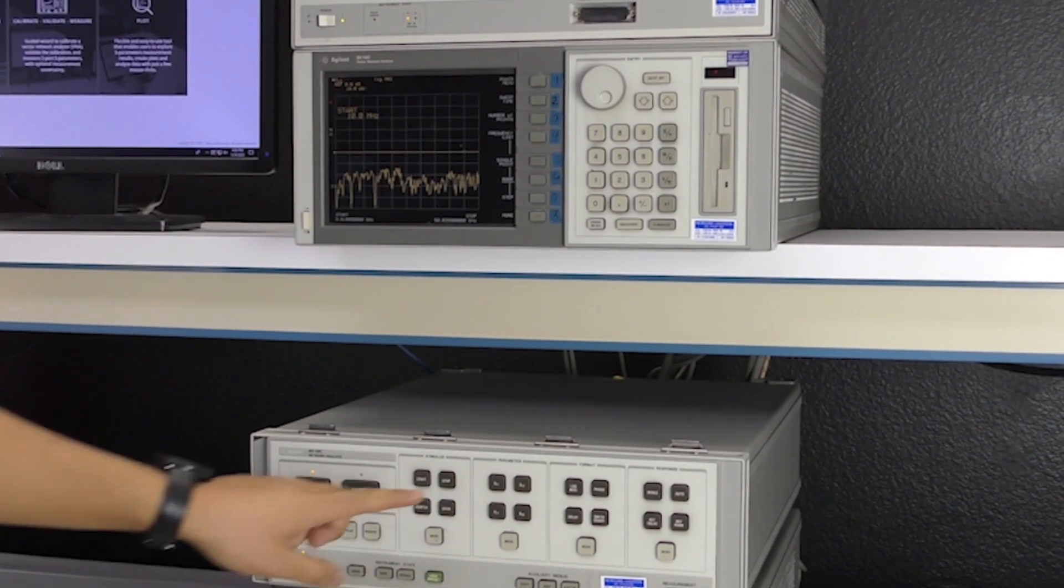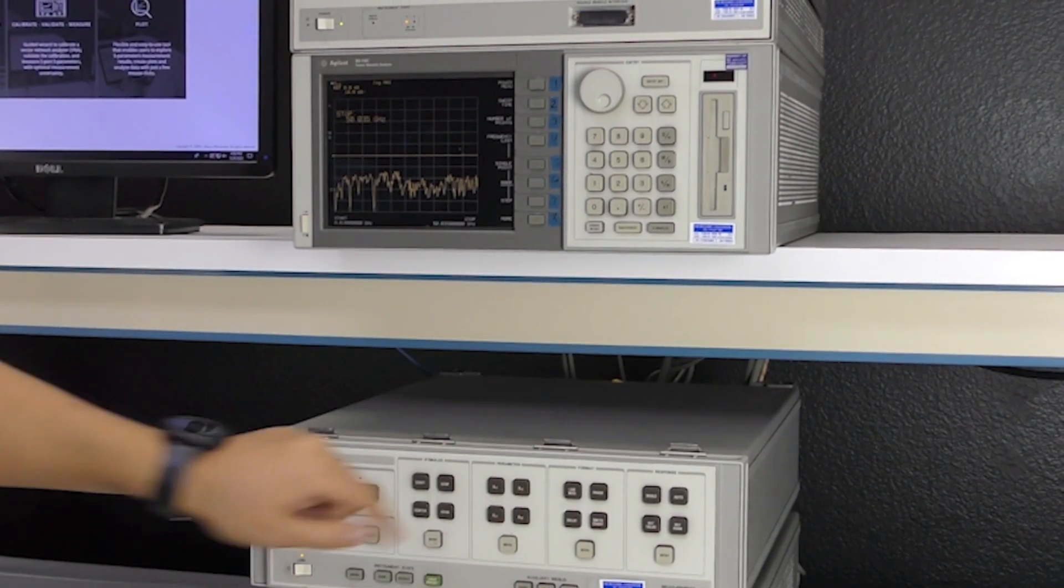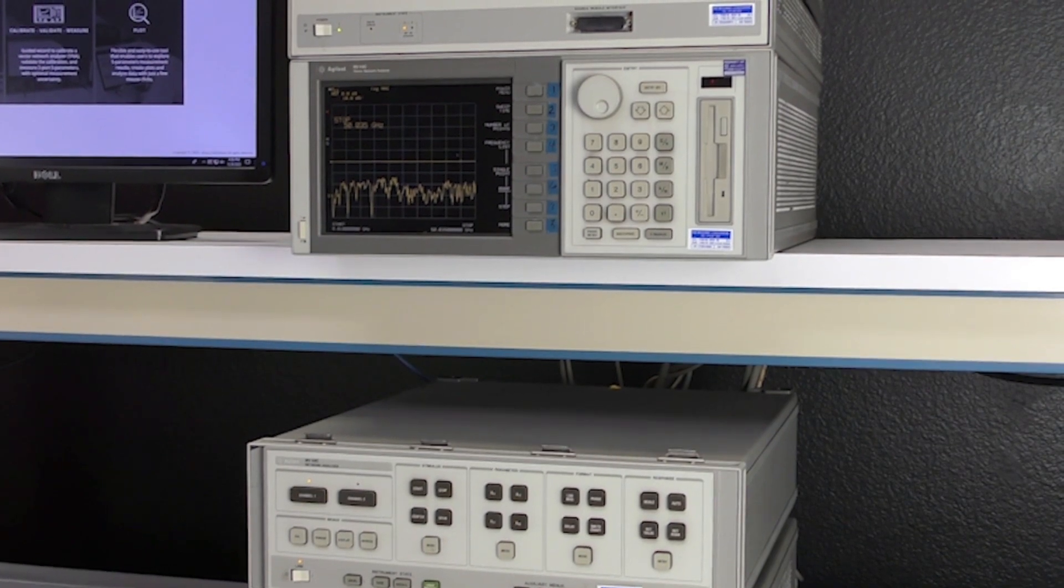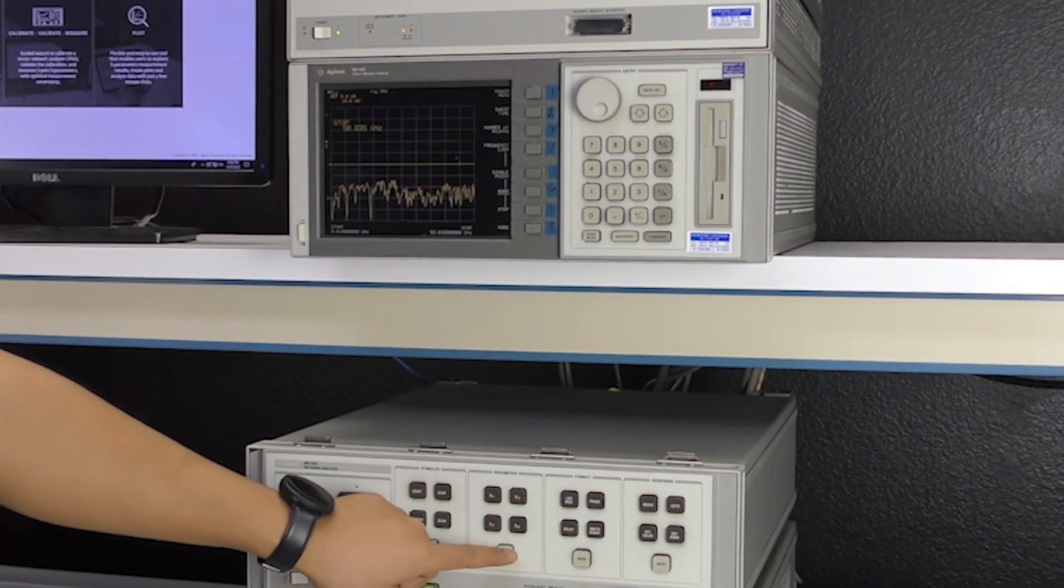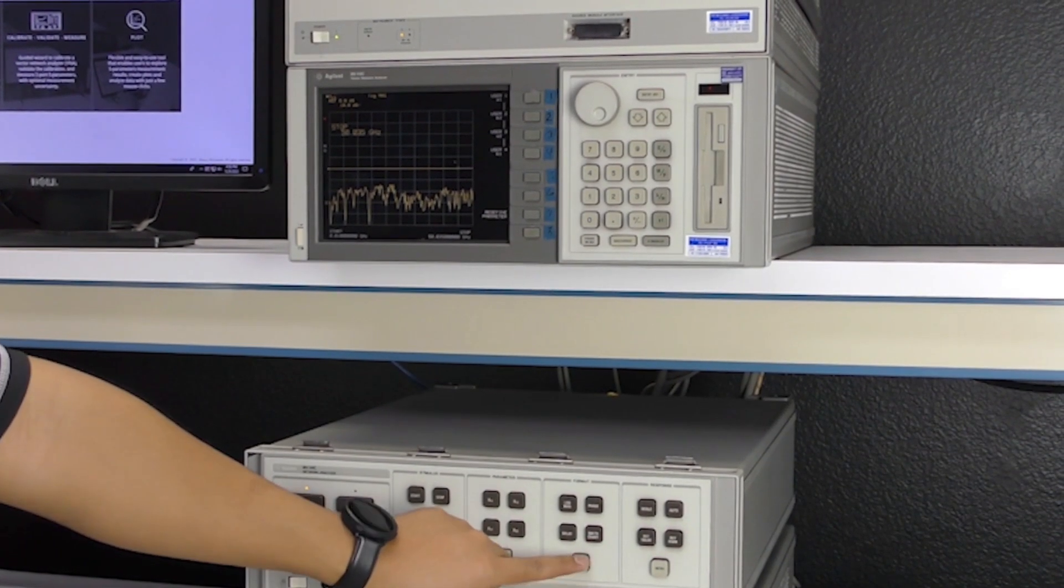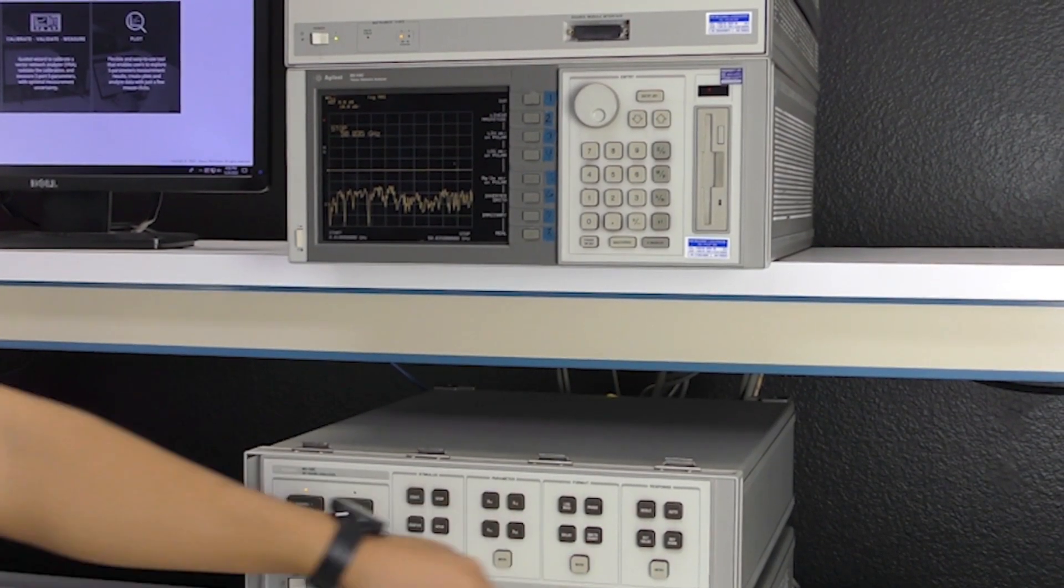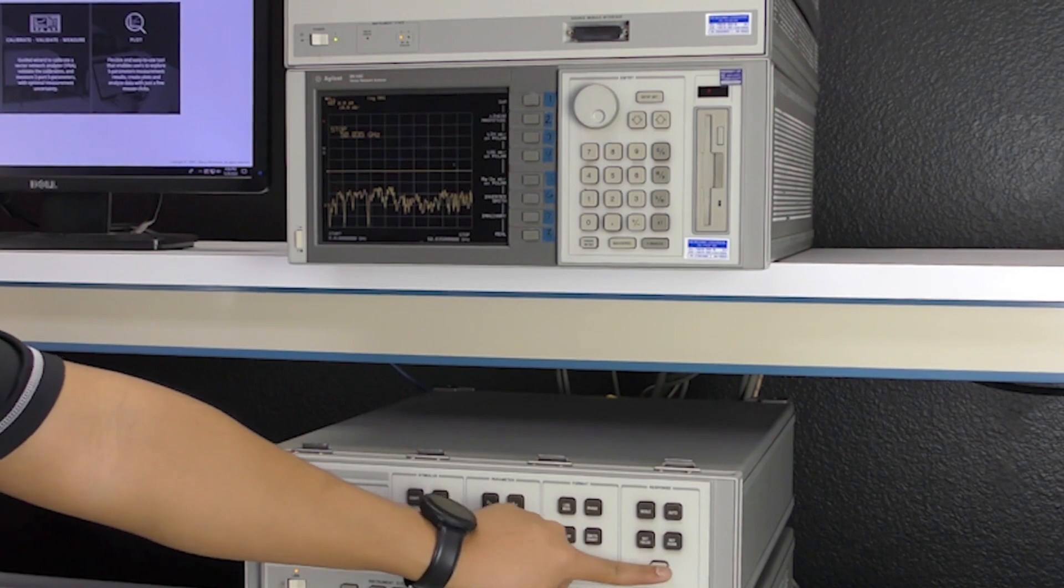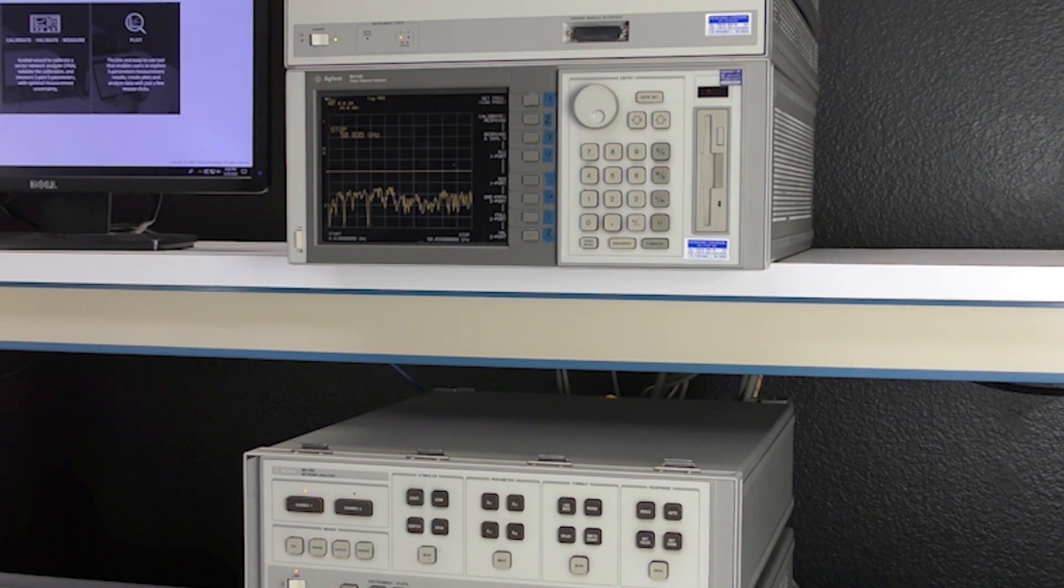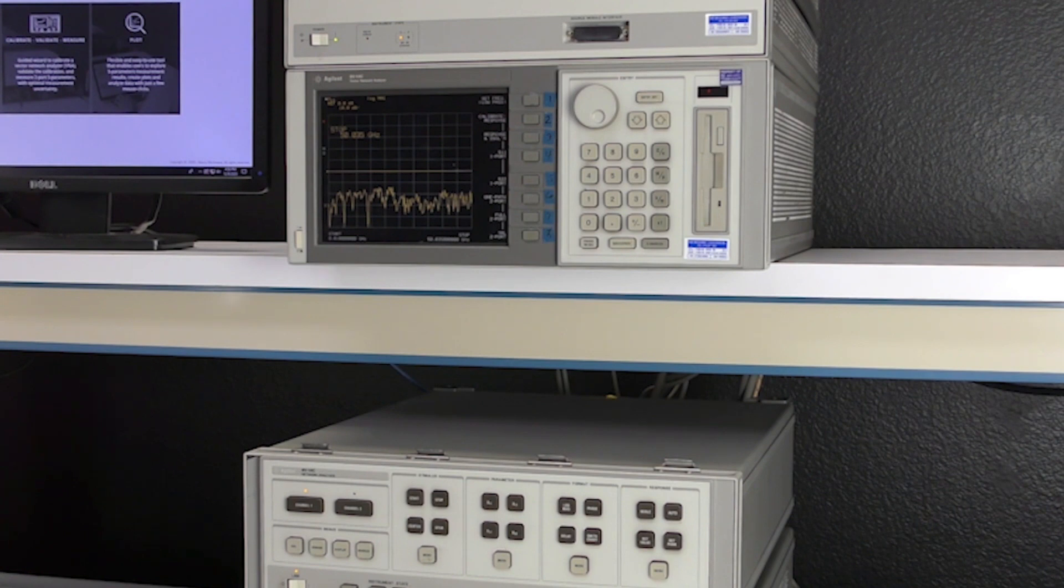You still have the S-parameter, format, and response menus to go through to make sure that all of your settings are dialed in properly. And don't forget, with having broken touch keys, this would make dialing in your calibration settings even more difficult. You may be already thinking to yourself that this can be a tedious process to go through every time you calibrate your VNA. Well, let's jump right into InSight to show you how much more friendly this process can be.